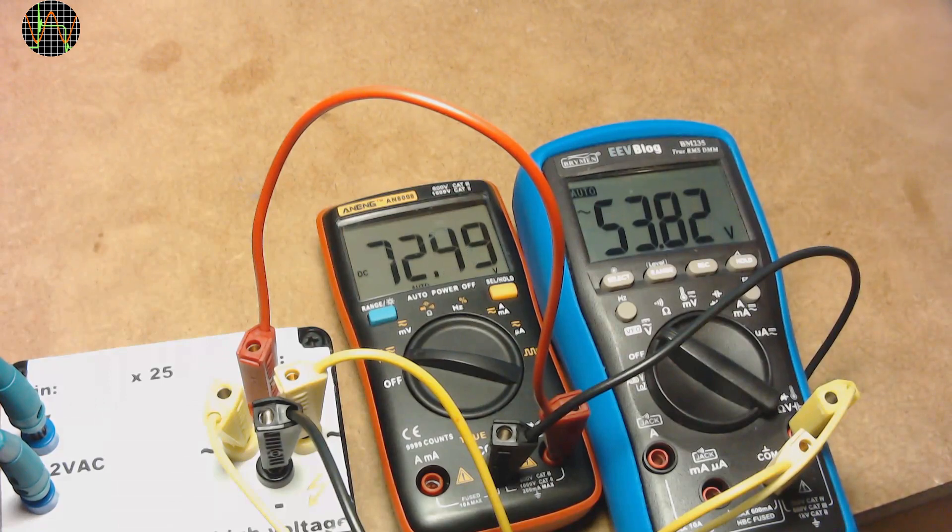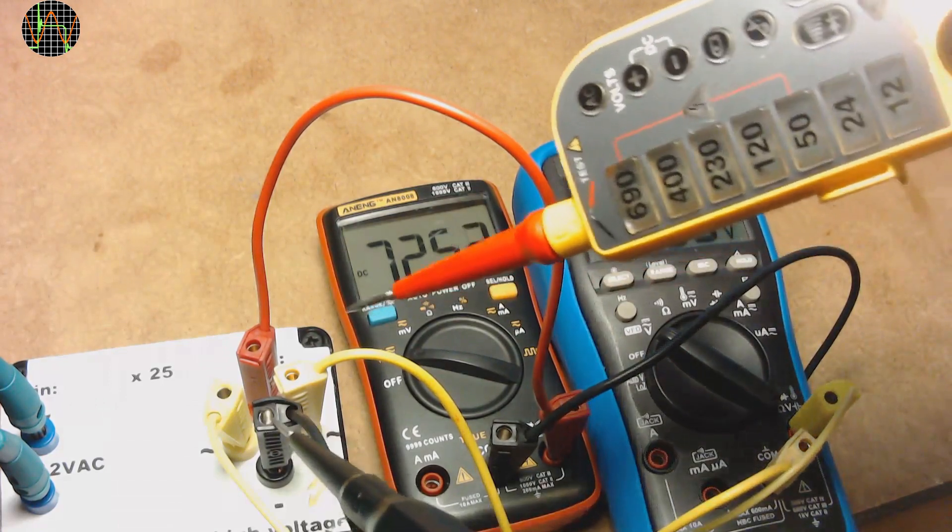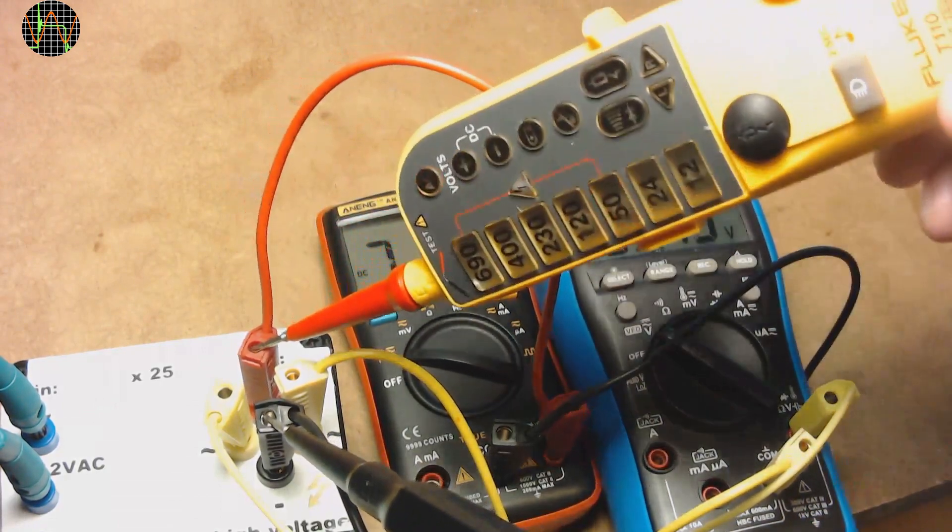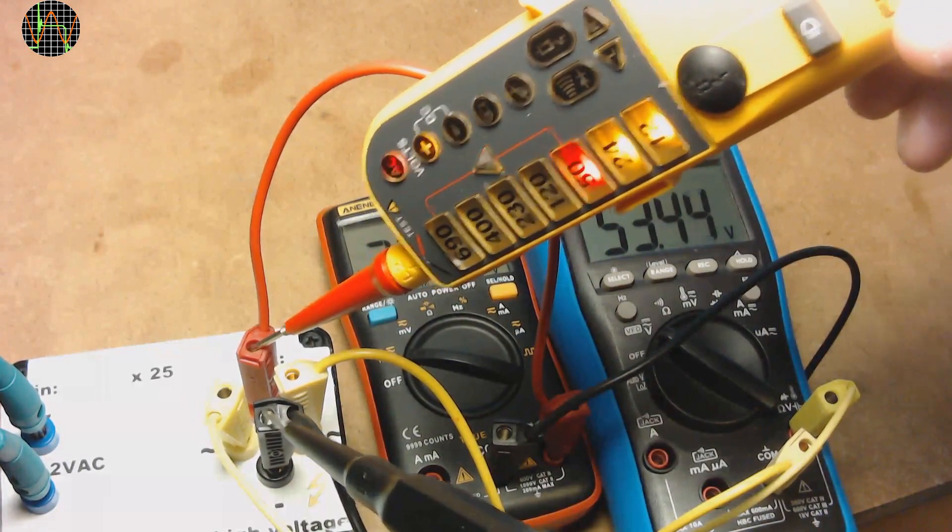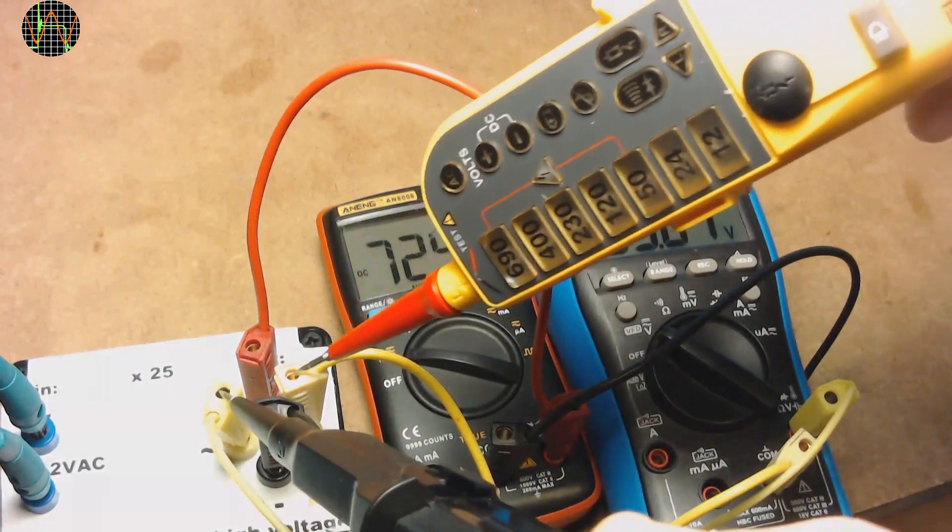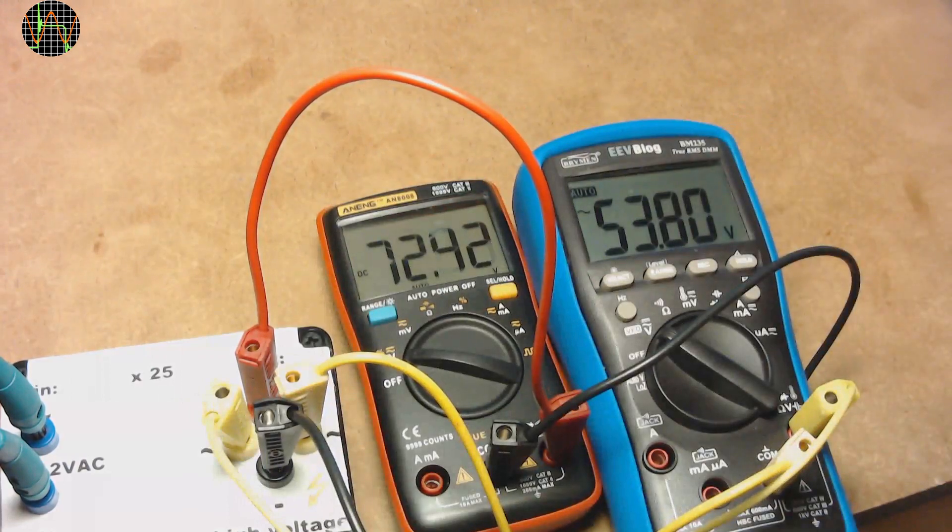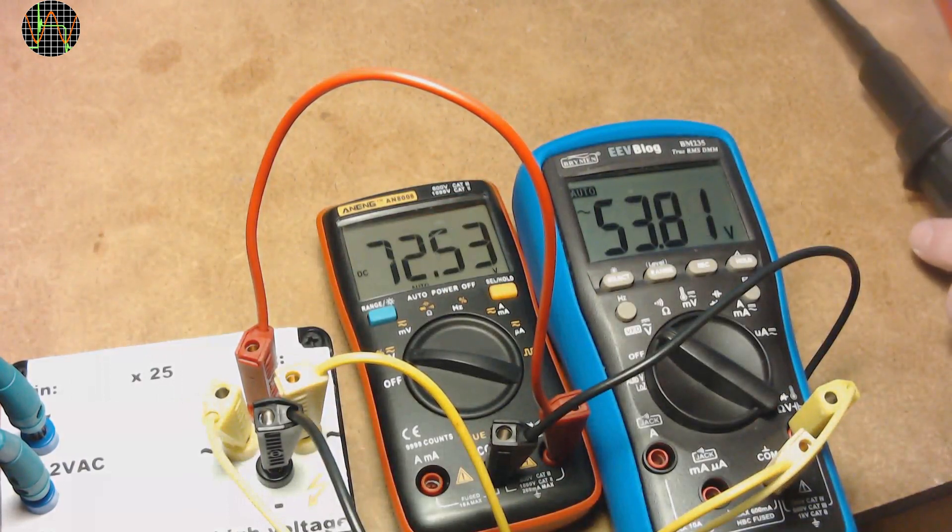With 73 volts DC, we get the lights up to and including 50 volts, the high voltage indicator and the DC polarity indicator. For the 54 volts AC, we get the same voltage indicators and the AC light and the rotary field indicator.